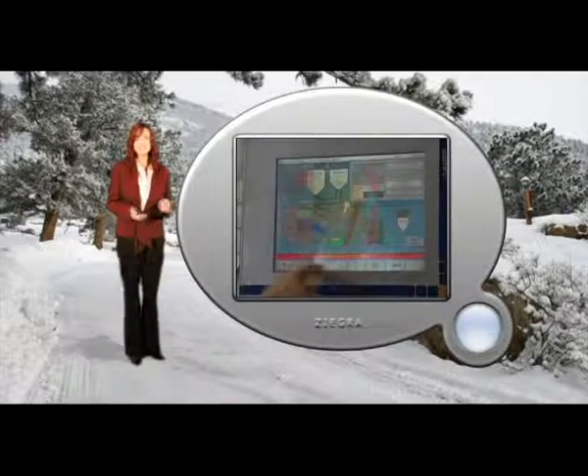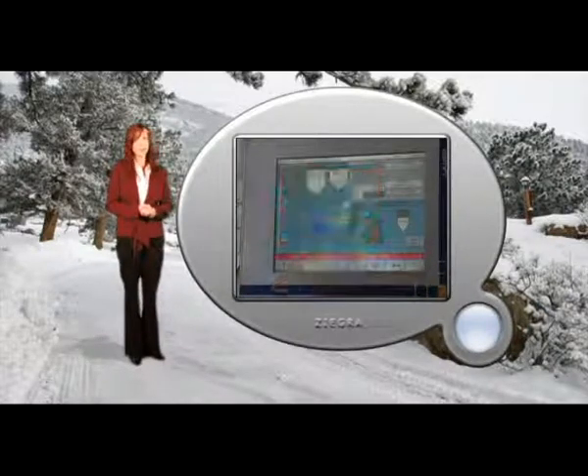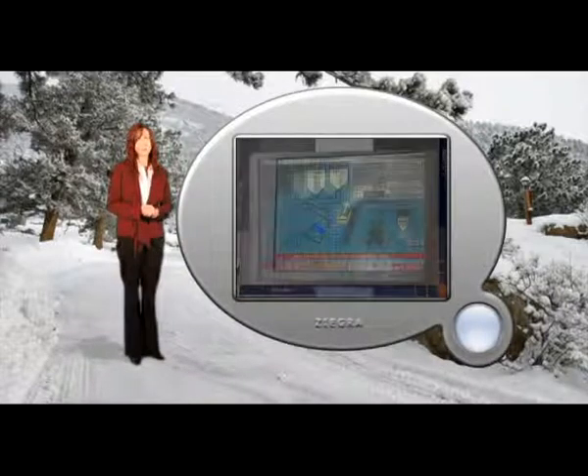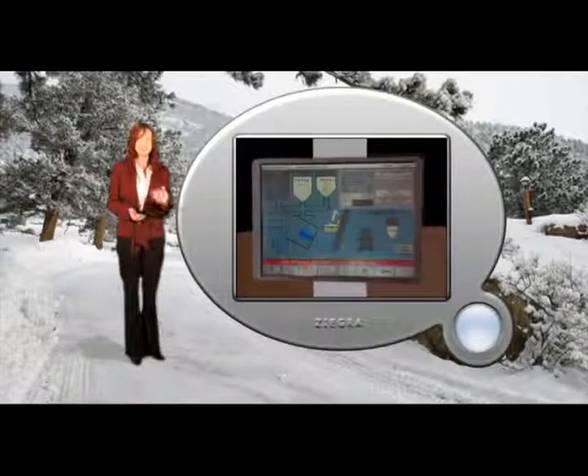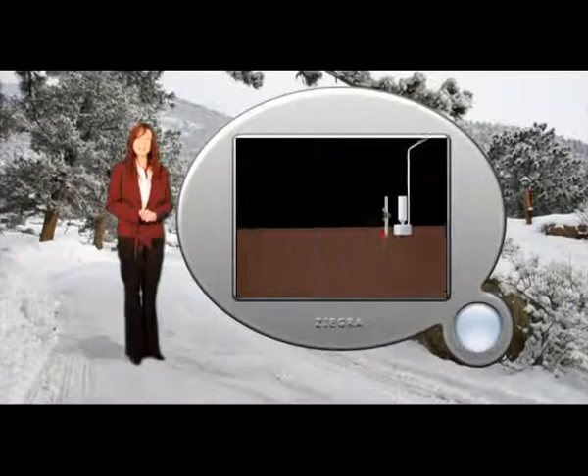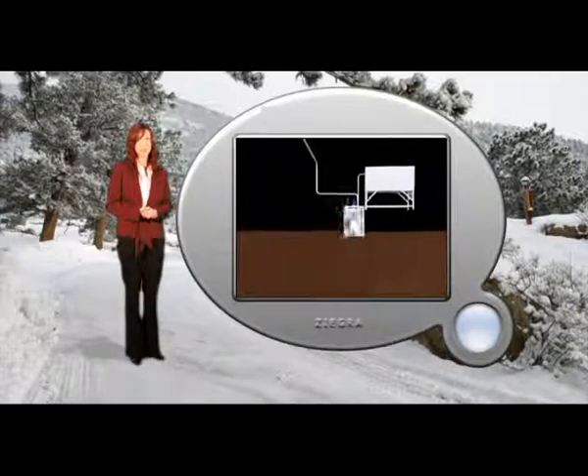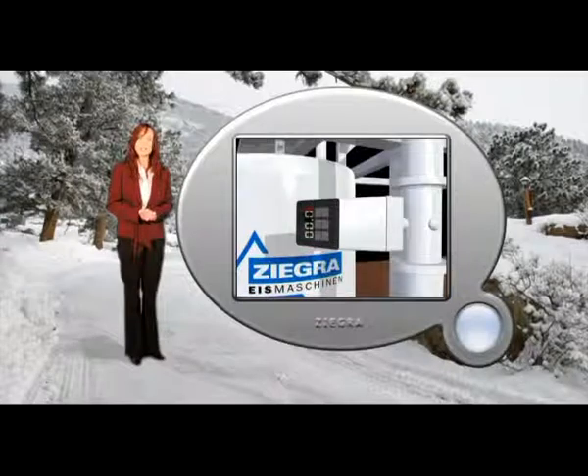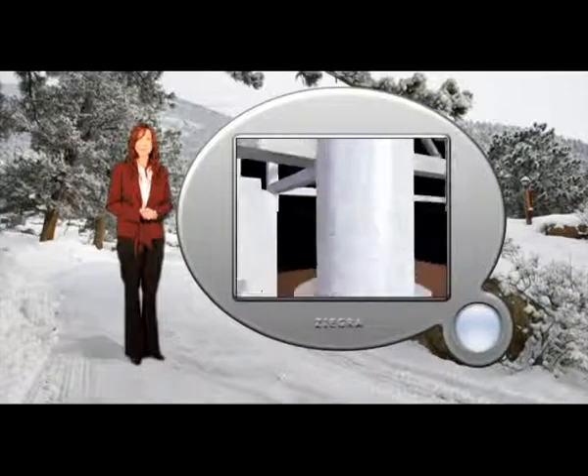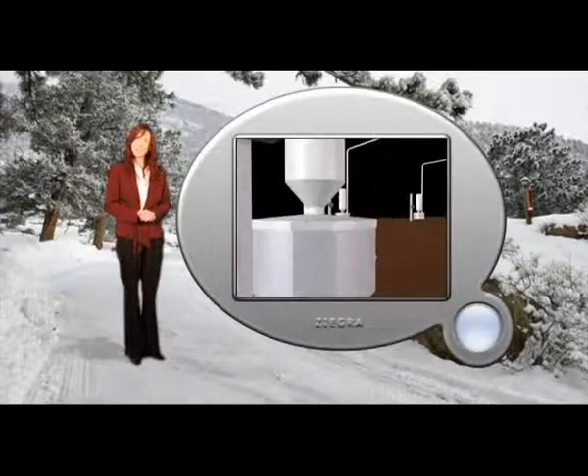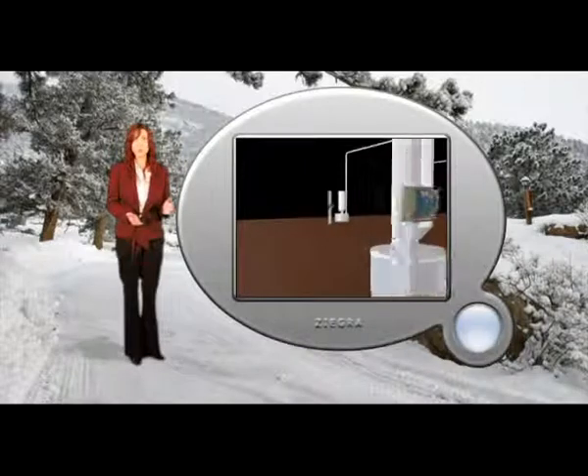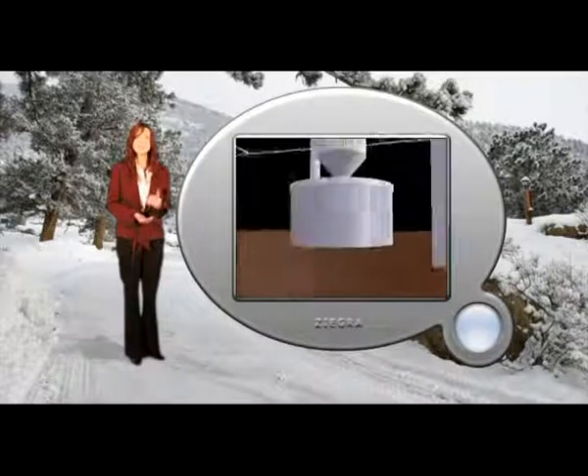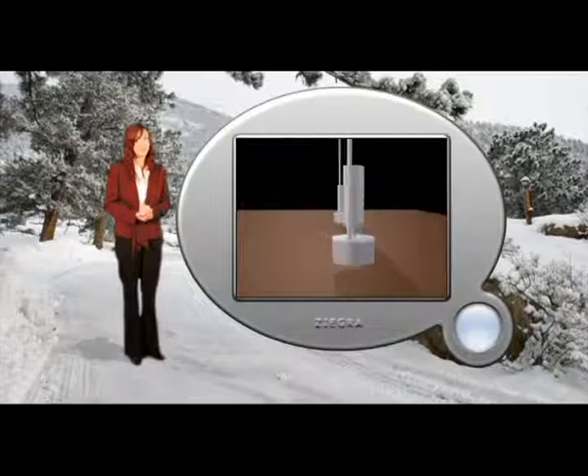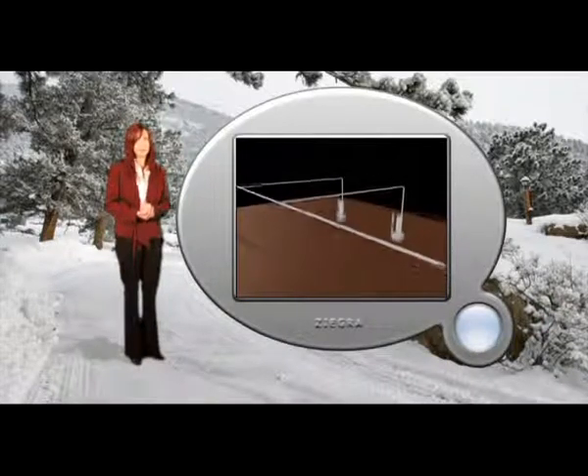In a typical installation, the mixer software or the operator enters the amount of ice needed per mix. Once this has been entered during the filling cycle of the mixer, a signal is sent to the StreamIce freshwater or SIF plant, which then automatically doses the correct amount of ice to the mixer. As soon as the ice is delivered, a confirmation signal is then sent back to the mixer. A single SIF plant can support multiple mixers in this way and always delivers the correct amount of cooling to each mixer in an accurate and repeatable way.